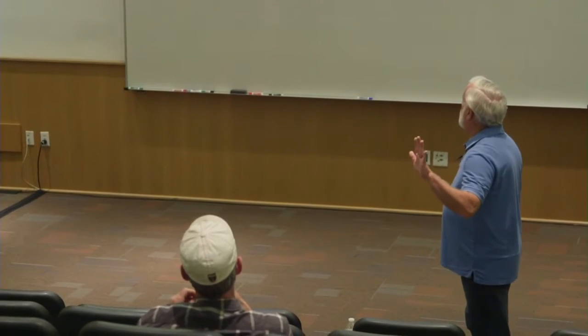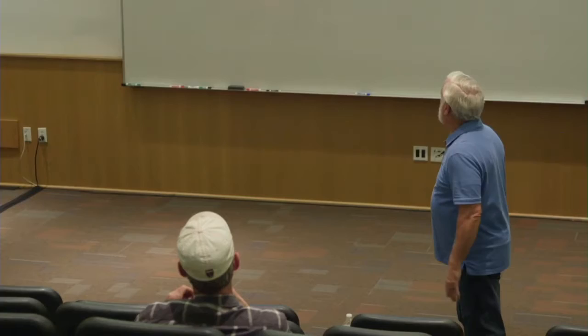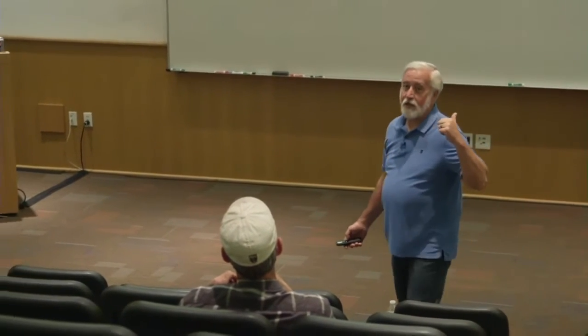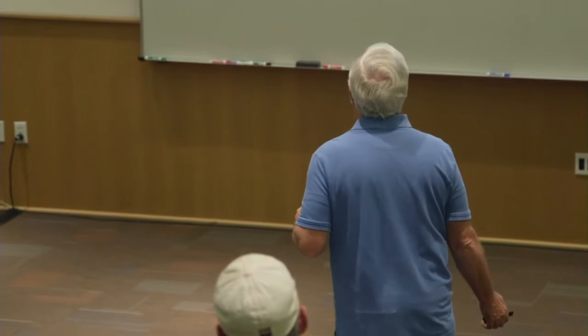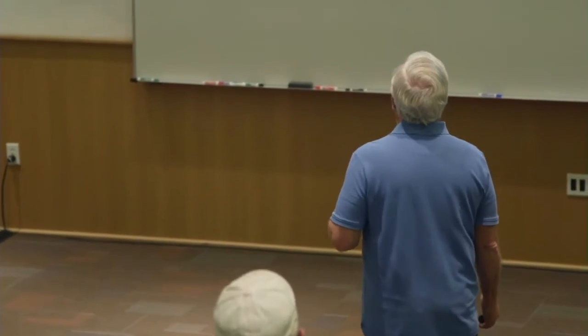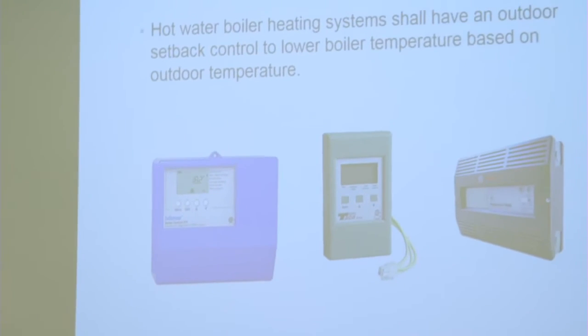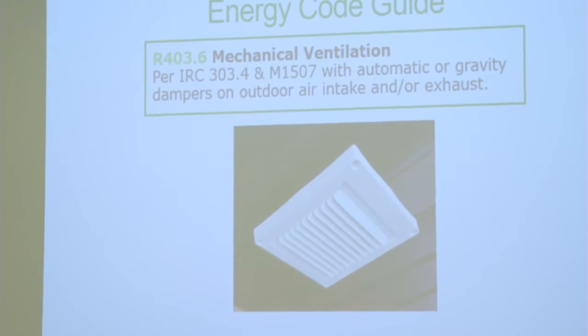Sizing, I'm not going to spend any more time other than I'm a firm believer in sizing. I learned to do manual J calculations by hand in about 1974. And I guarantee you, if you do a proper load calculation, it'll work. And you'll put a properly sized piece of equipment, and it'll work well, and people will be comfortable with it. There's your boiler outdoor reset controls. That's what they look like.